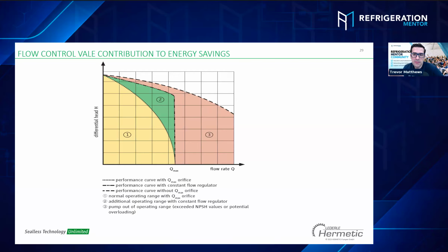I do have a question here from Darwin. What is the difference between NPSHA and NPSHR? Do you know? Is there a difference? Okay, we have the pump, we have the liquid level. R is when the liquid just goes across the pump. It's like a differential. It's when you size the differential pressure of the pump. So one is the level, and then one is the differential? Yes, basically.